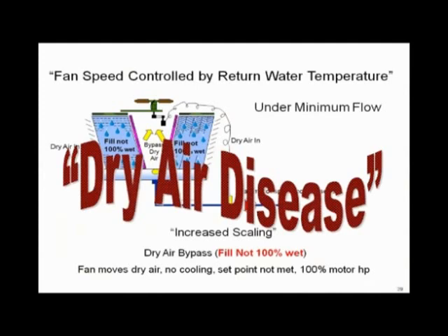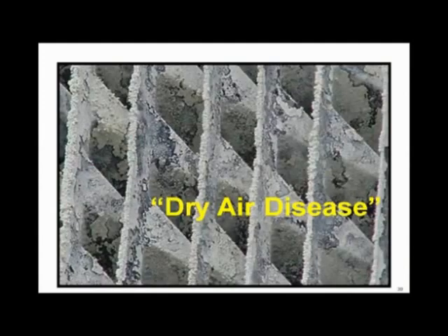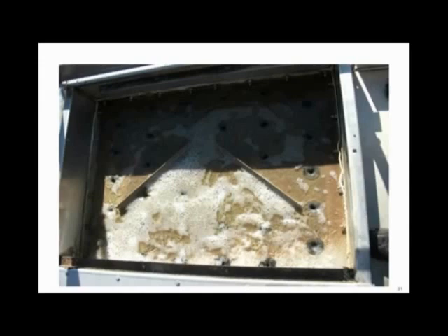What does it look like when you underflow a tower? You get dry and wet zones side by side, and right in between you start building up rocks — scale deposits. All of that can be solved with a weir dam. Here's another picture of a hot deck with a weir dam for 50% turn down — it ensures there are no passages where dry air can get through, so any air entering will always reach a wet section of fill.